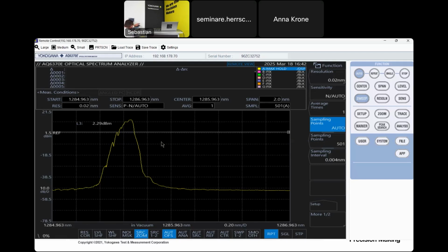If we now change the pulse width and therefore increase the duty cycle, we see a little shift in the spectrum due to the higher energy that is applied to the laser, but the peak power is still the same and is not changing with different duty cycles. So we see that with this mode, really the pulse power of the peak is detected.